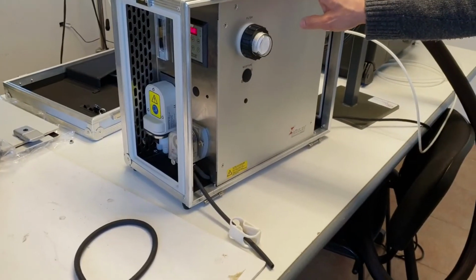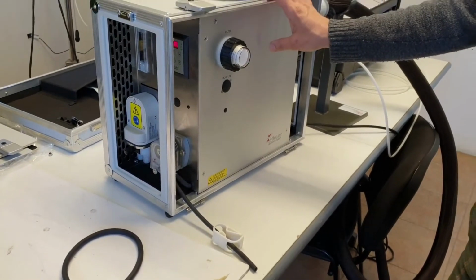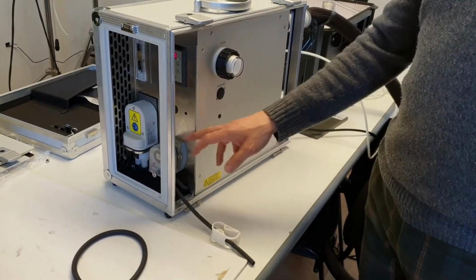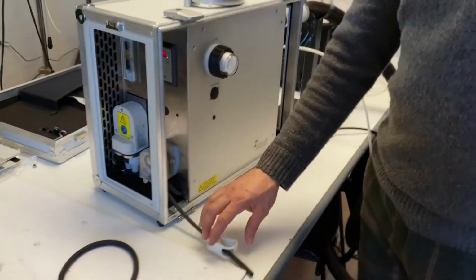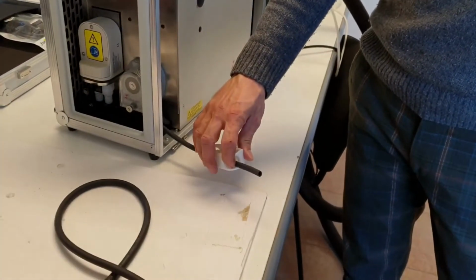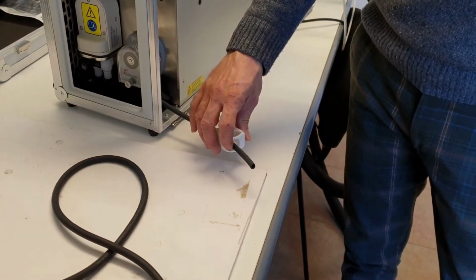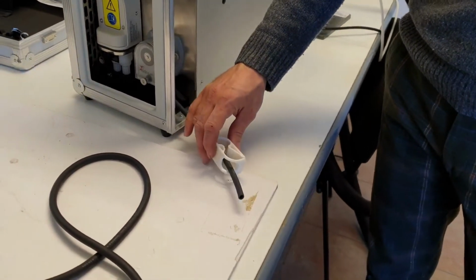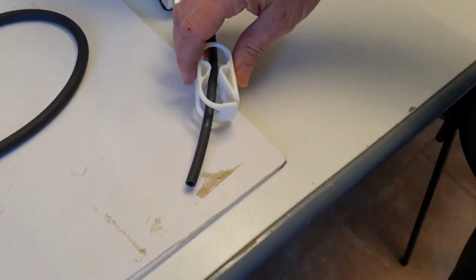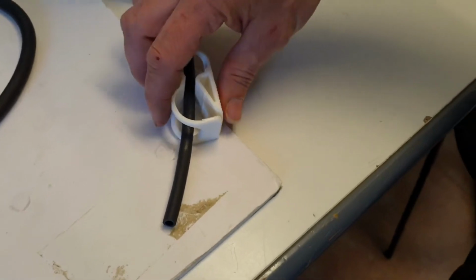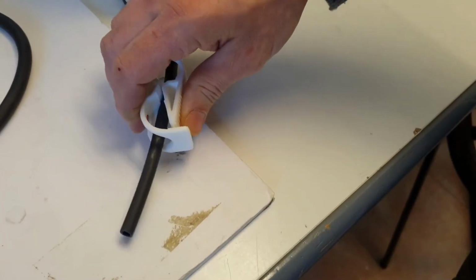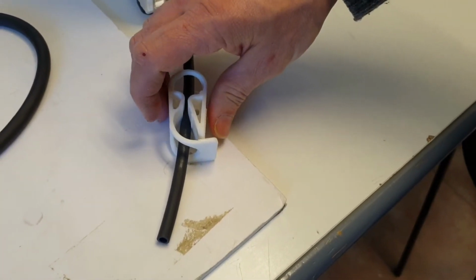There is a chiller inside the conditioning unit with a liquid pump. This is the outlet of the liquid. It has to be open when the system is on and closed when the system is off and during the transportation.